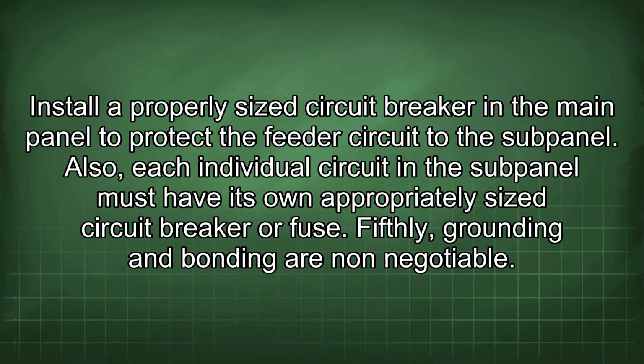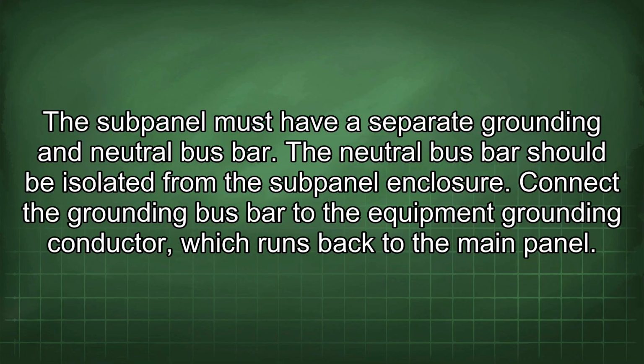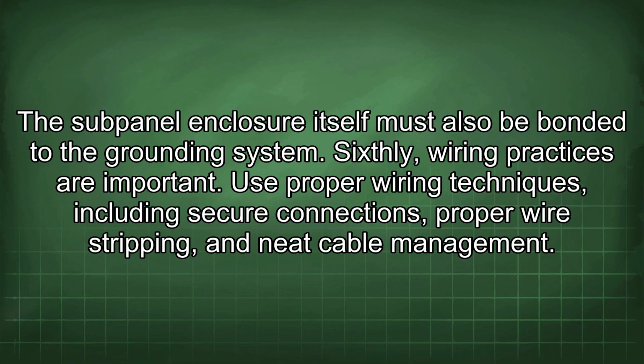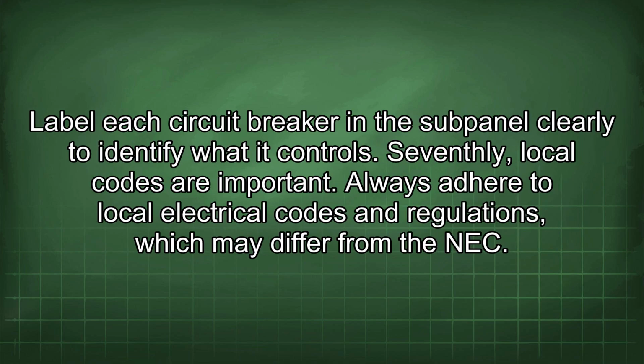Fifthly, grounding and bonding are non-negotiable. The subpanel must have a separate grounding and neutral bus bar. The neutral bus bar should be isolated from the subpanel enclosure. Connect the grounding bus bar to the equipment grounding conductor, which runs back to the main panel. The subpanel enclosure itself must also be bonded to the grounding system. Sixthly, wiring practices are important. Use proper wiring techniques, including secure connections, proper wire stripping, and neat cable management. Label each circuit breaker in the subpanel clearly to identify what it controls.